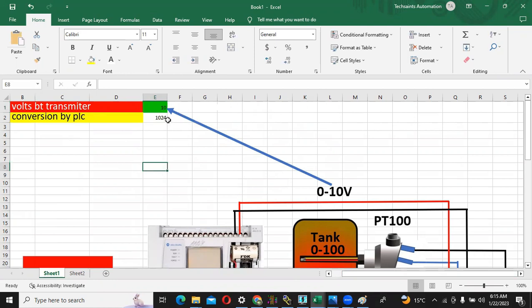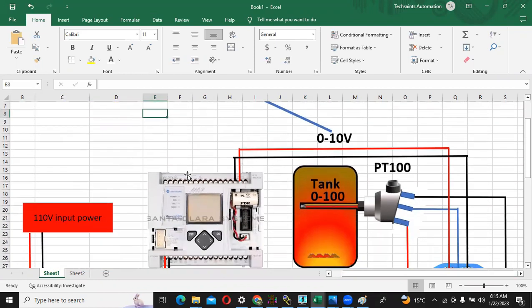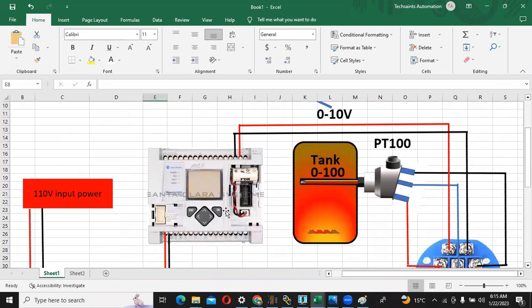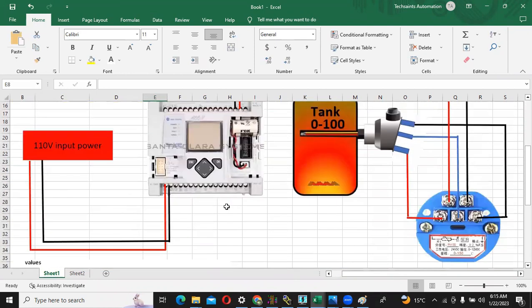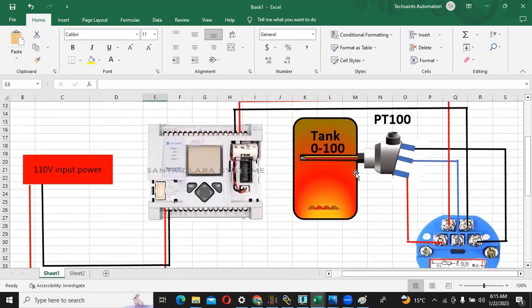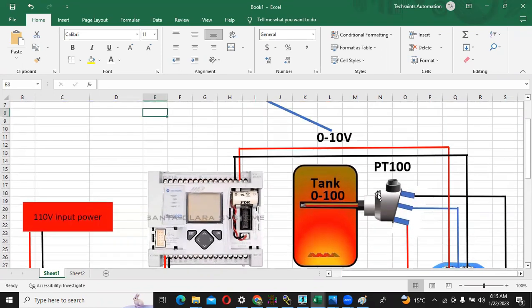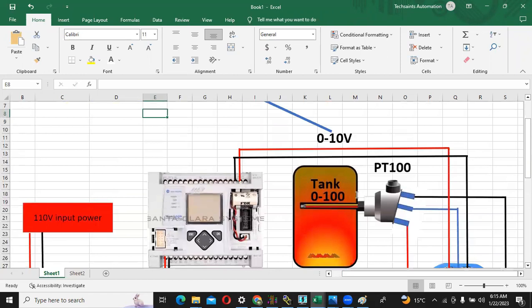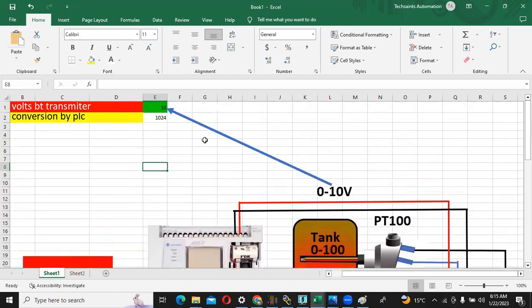This is the conversion method of MicroLogix 1100. So now what is happening, suppose temperature 0 to 100 is coming to this PT100, and the transmitter is converting 0 to 100 into 0 to 10 volt. This 0 to 10 volt is going to the PLC and PLC is converting this value from 0 to 1024.